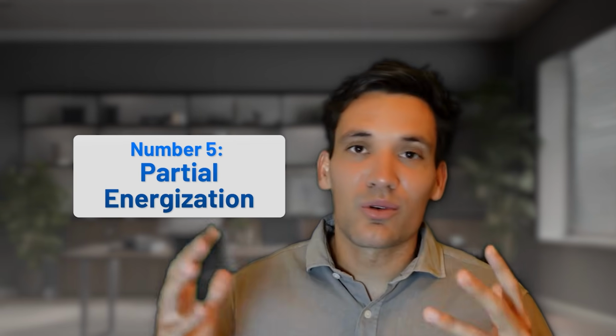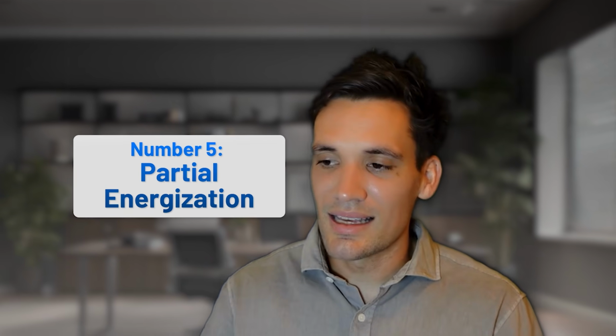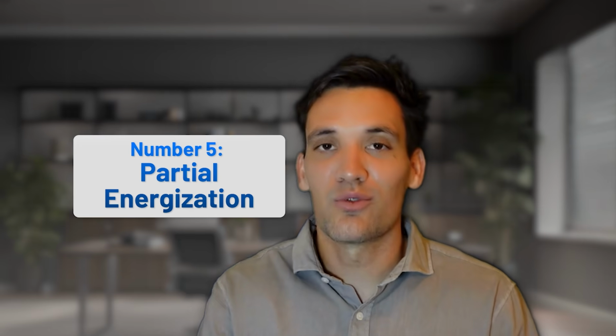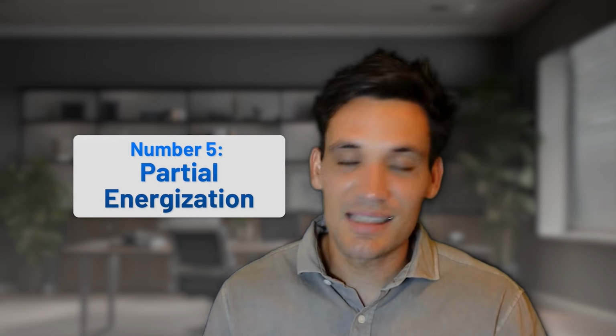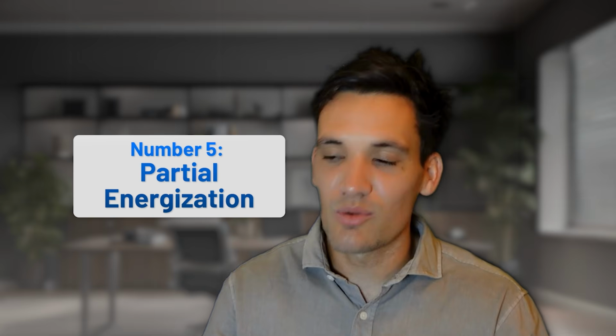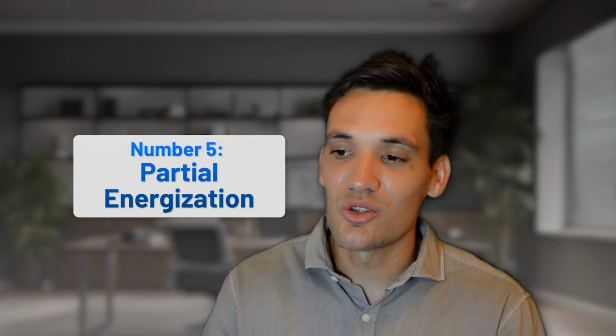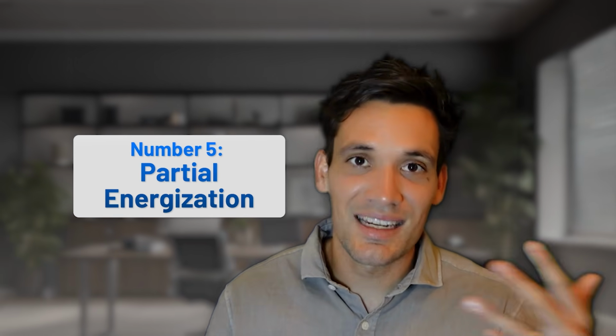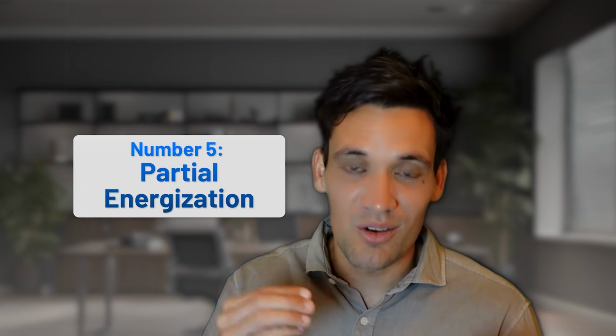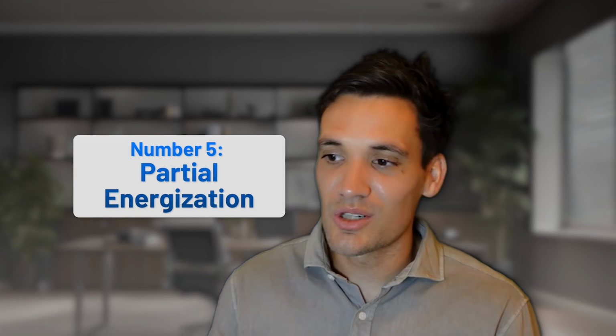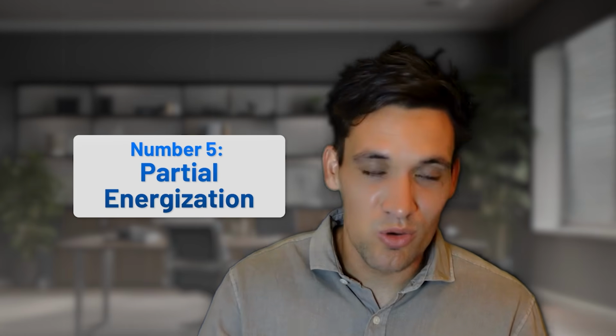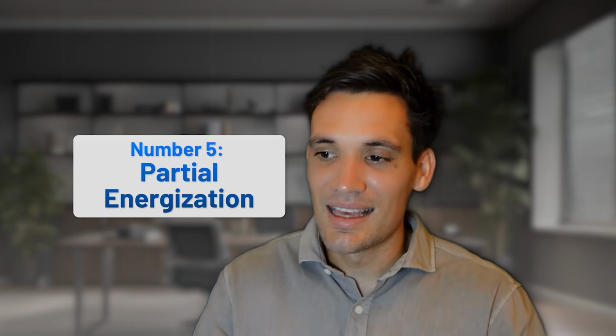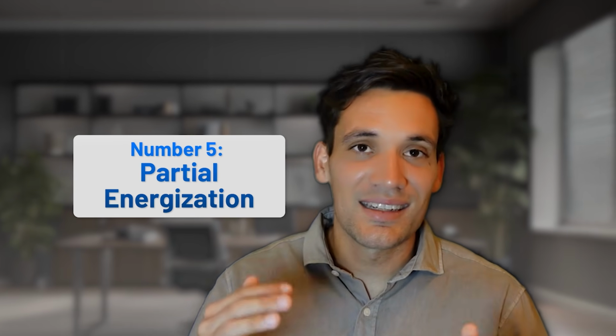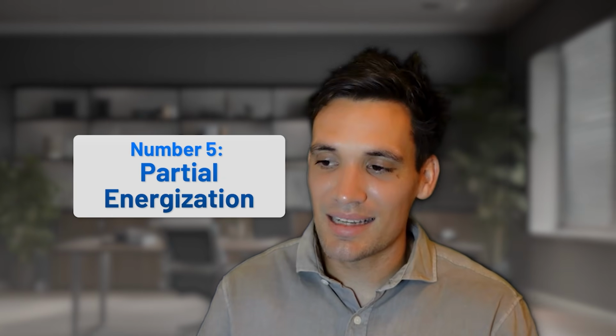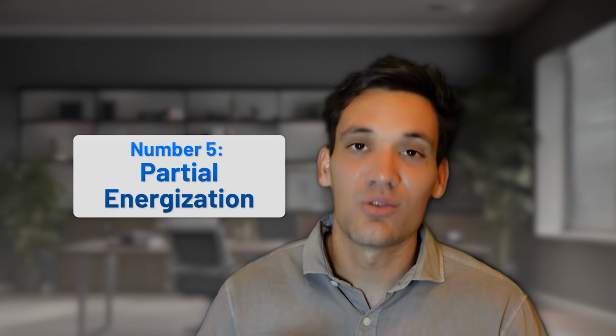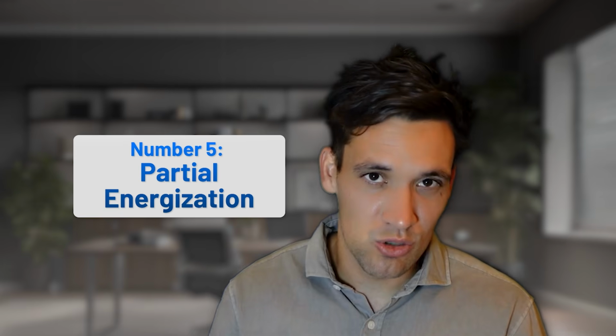In theory, project managers always have this idea that you can start commissioning before the construction is fully complete. And yes, it does work to a certain degree, but when you start turning the power on, you cause all these other cascading impacts, all these challenges of working on a partially energized system, which causes all these issues with permits to work, hazards, delays, and temporary feeds can significantly impact the actual construction works, not to mention the dangers it exposes the workers to.